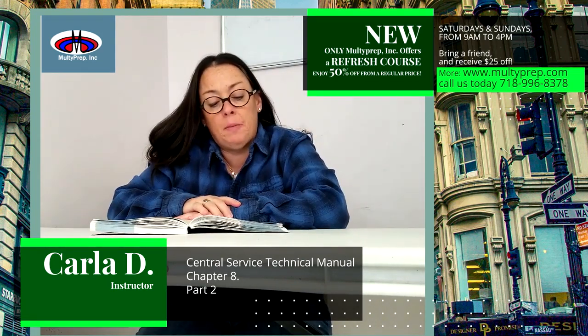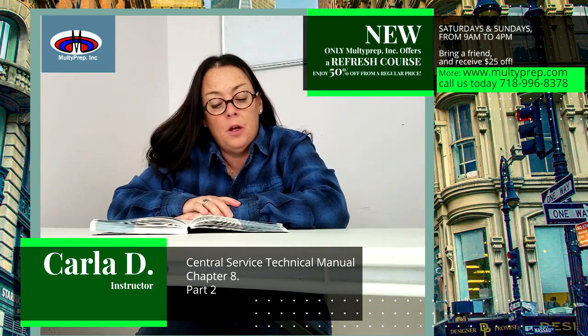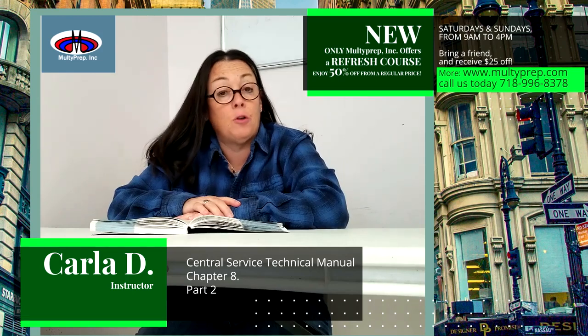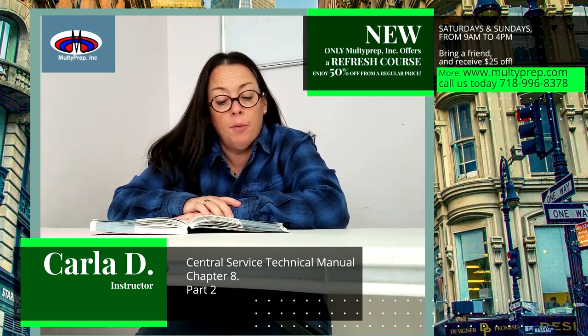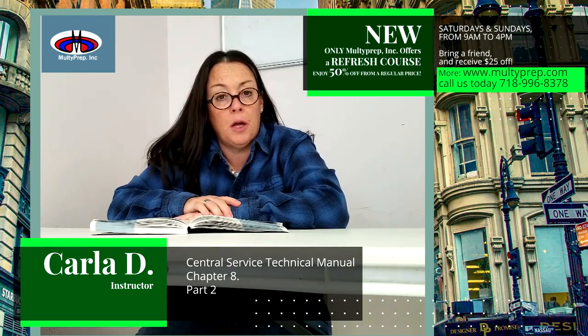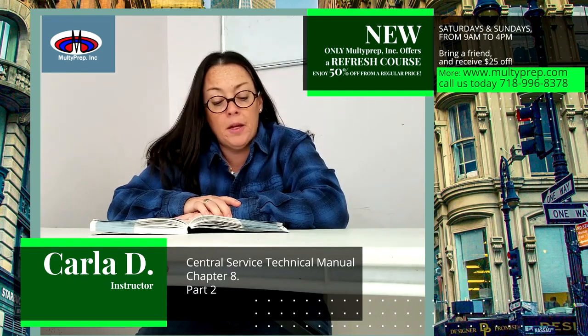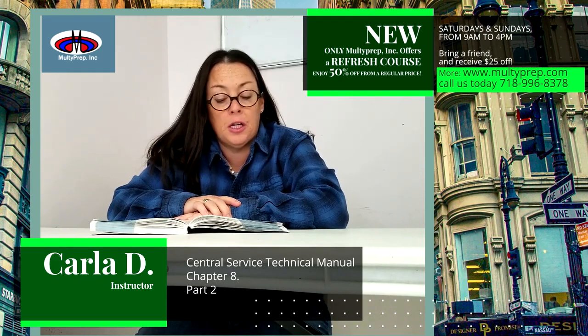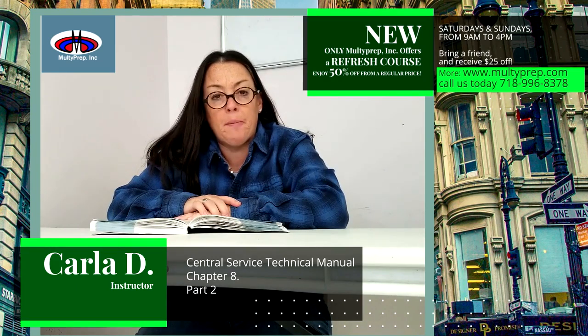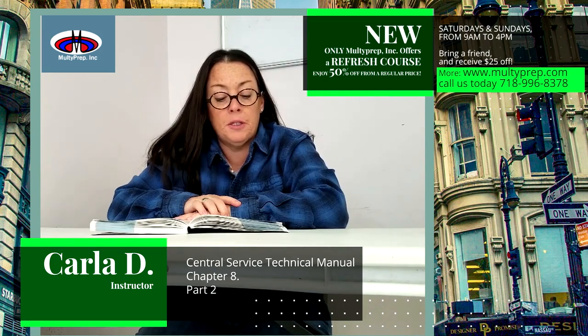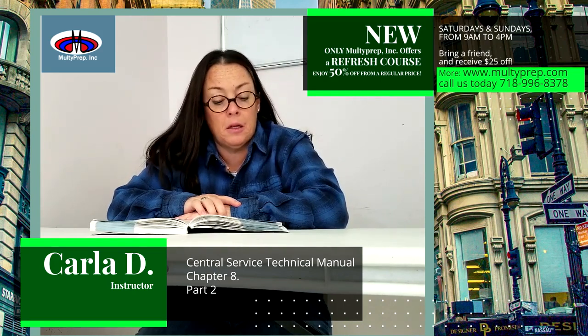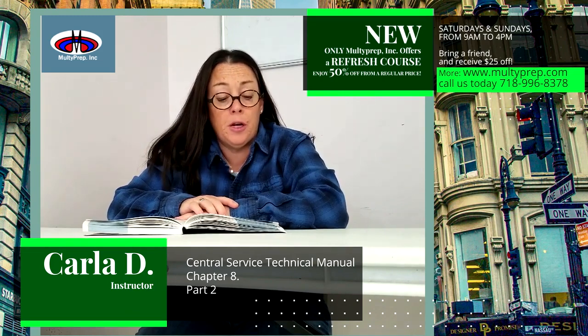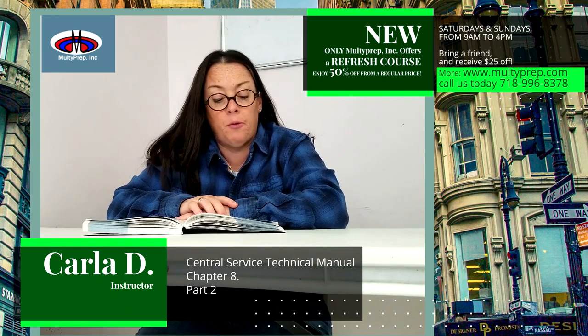Many types of soil can be present on reusable devices. When soil, especially blood, is allowed to dry prior to cleaning, it becomes difficult to remove. See Figure 8.34 for an example of this. Blood flows onto instruments, joints, grooves, and other difficult to clean locations. It then coagulates and dries to create a significant challenge to cleaning. Soil adheres to microscopic irregularities in the surface of instruments and has to be manually and mechanically scrubbed away or chemically treated. Otherwise, it could result in the formation of biofilm.